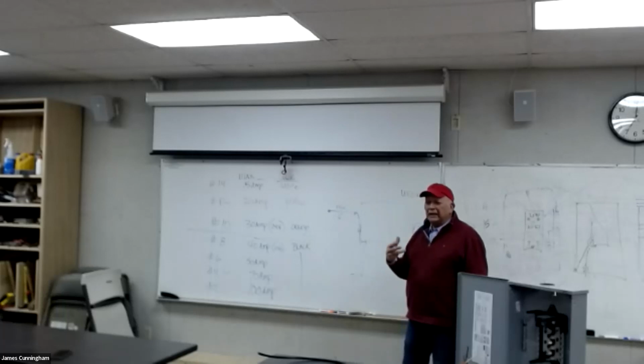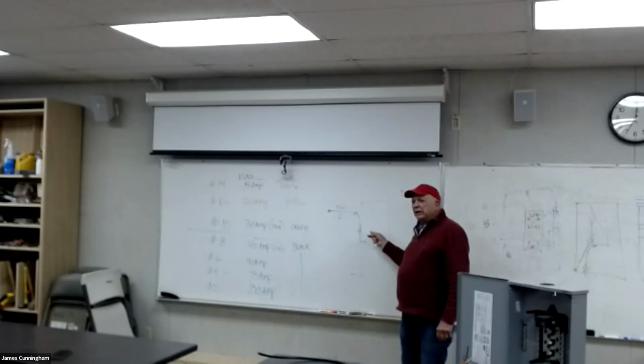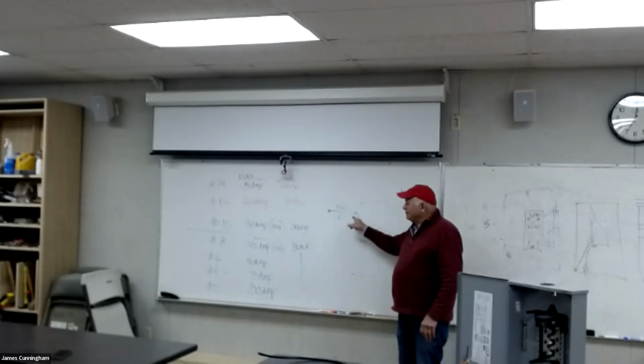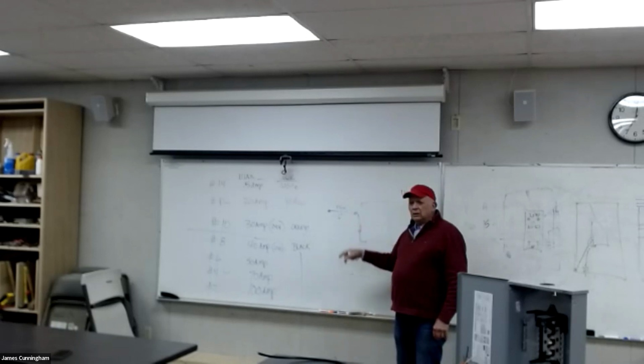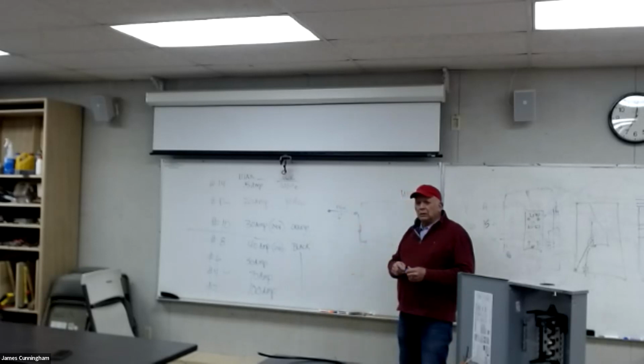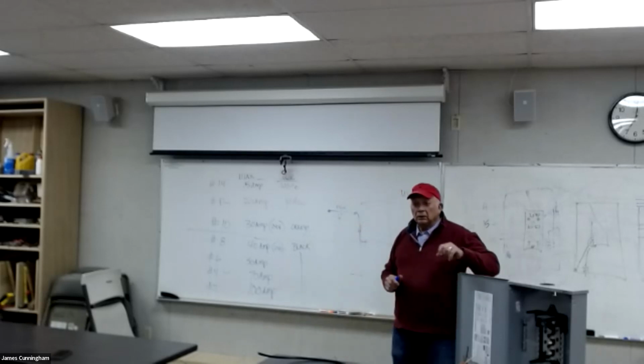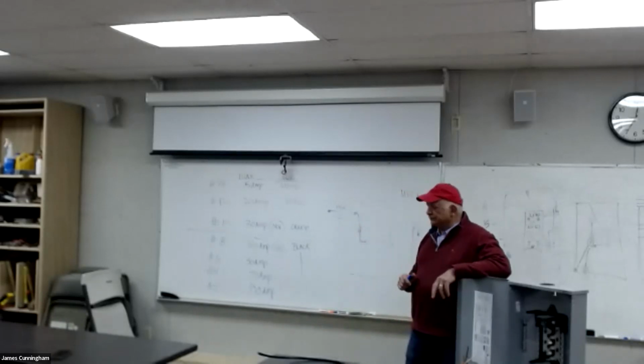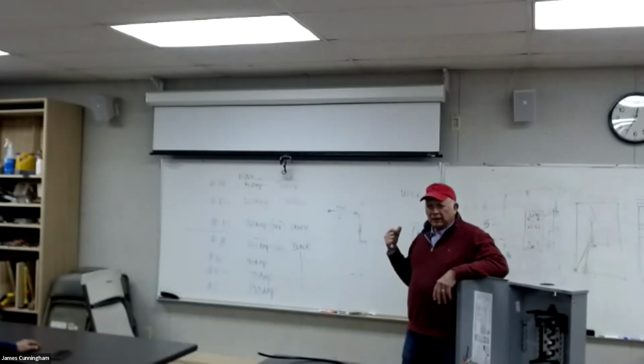So if you're doing a retrofit or upgrading your service where you're changing from 100 amp to 200 amp, a lot of times you're going to have to do 2 grounding rods. Do you know why that requirement's there? Why do they need the redundancy? Why do you have to have 2? Because it's a lot of electricity, and in some places you're not getting as good a grounding as you would from a UFER ground.